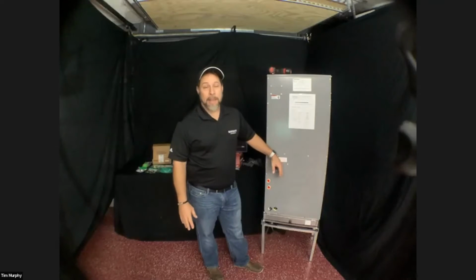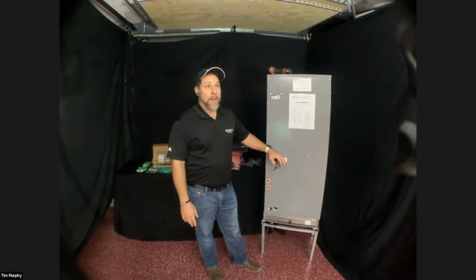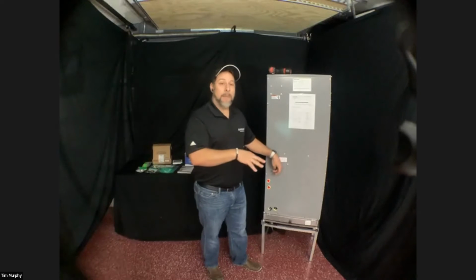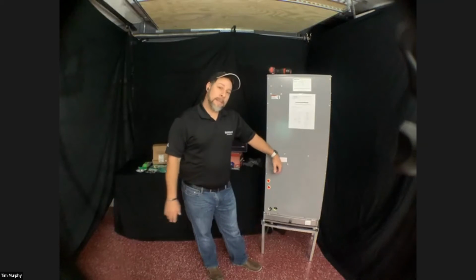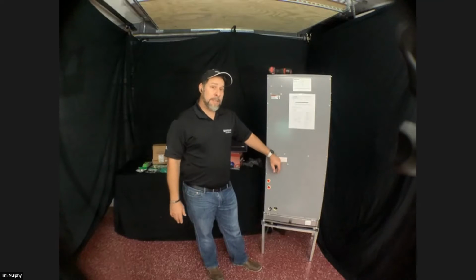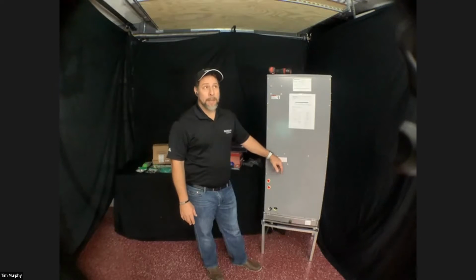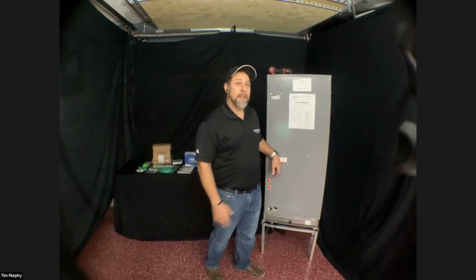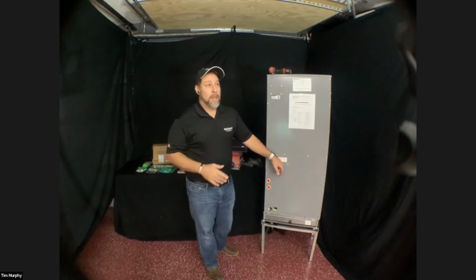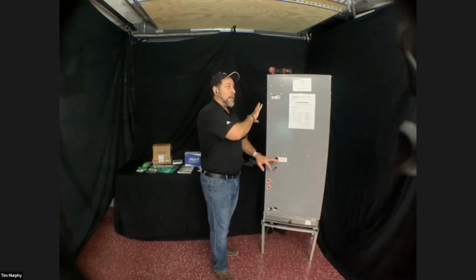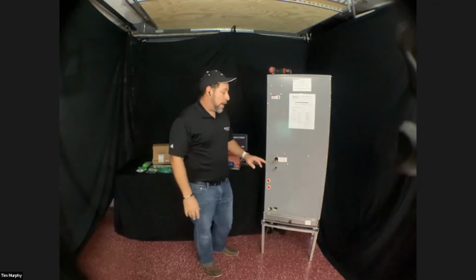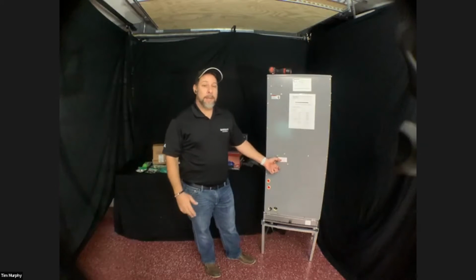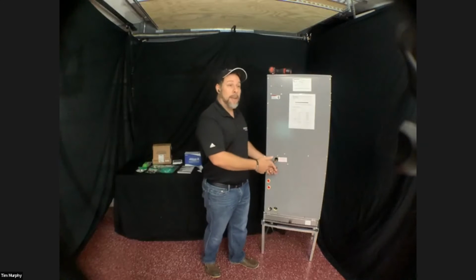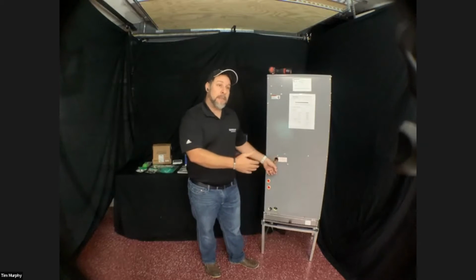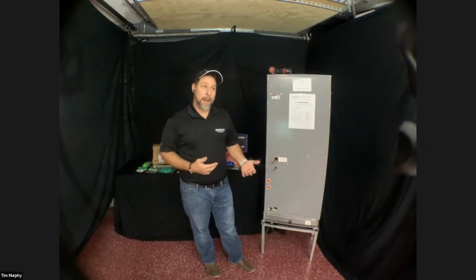You're going to have to run its own copper. Not only because the existing copper is not going to be insulated, but also the pipe sizing is going to be different as well. On a 3-ton system, this is only 5/8 and 3/8, and I believe the 3.5-ton system is also 5/8 and 3/8, and then the 4-ton I believe is 3/4. They only come up to a 4-ton, so unfortunately this is not going to be available on a 5-ton. But that being said, piping is something that, unfortunately, if you're going back behind another conventional style split system, is going to be something you'd have to figure into the price.